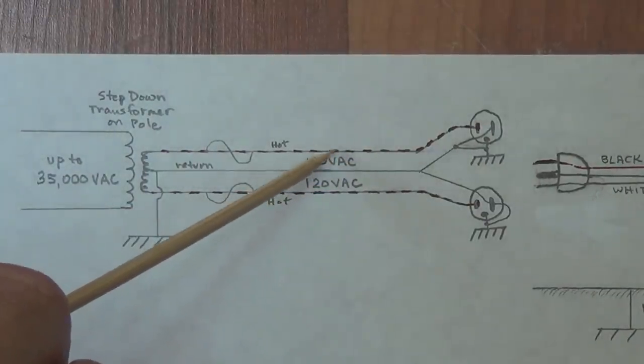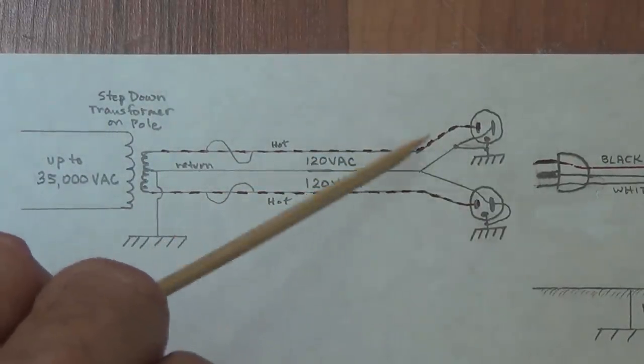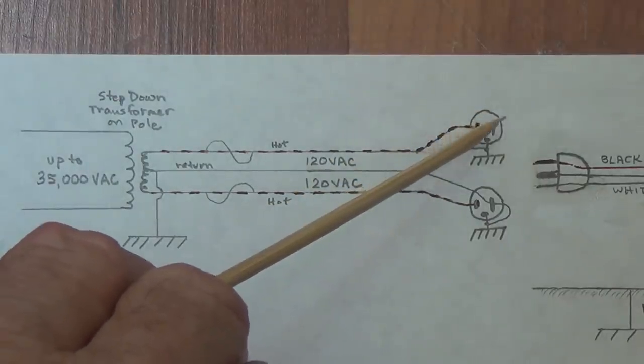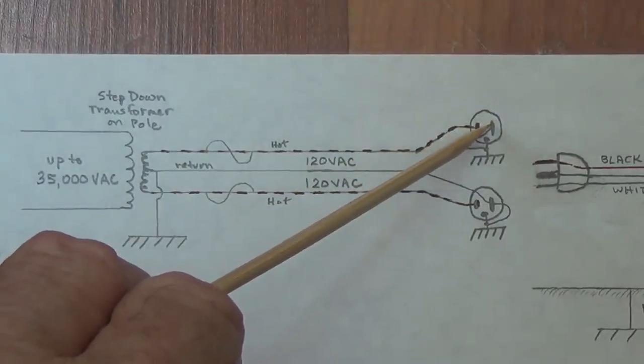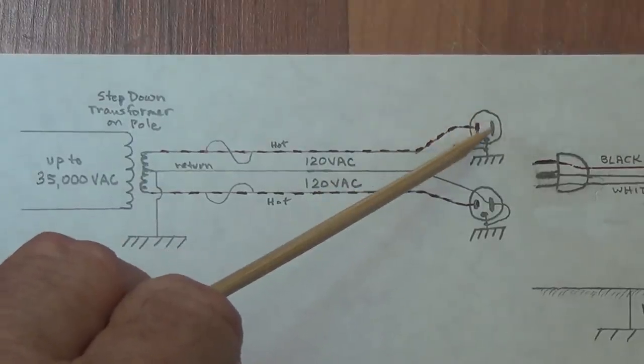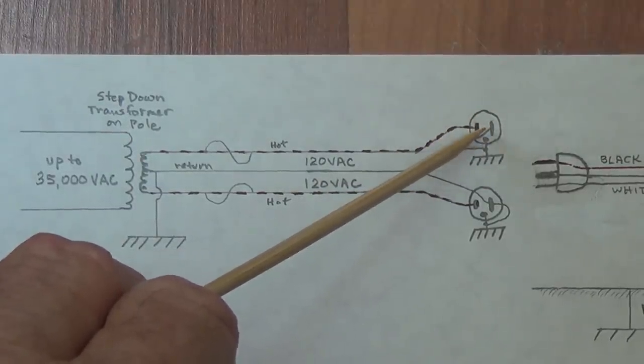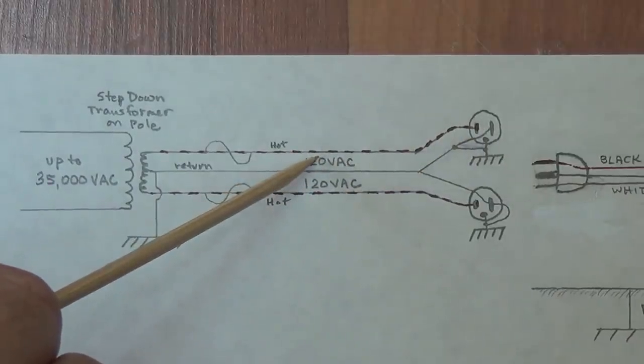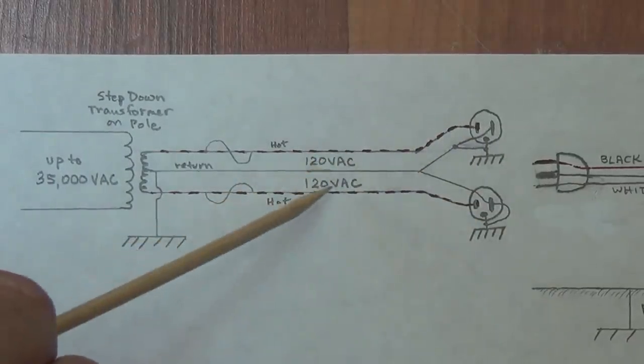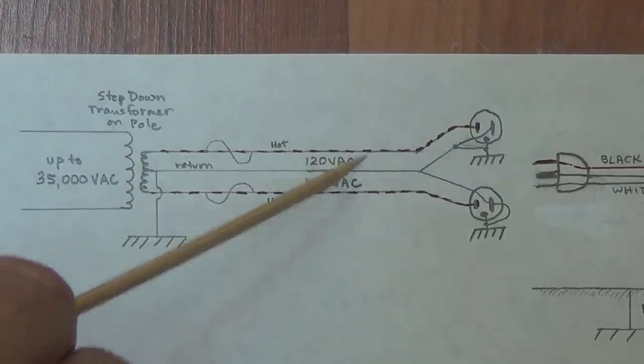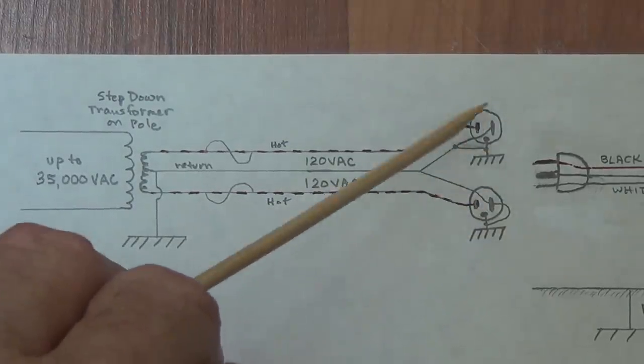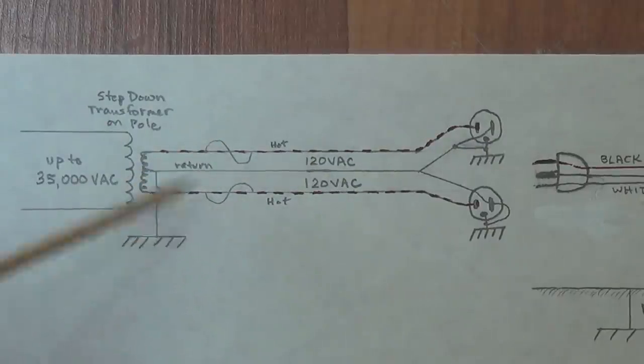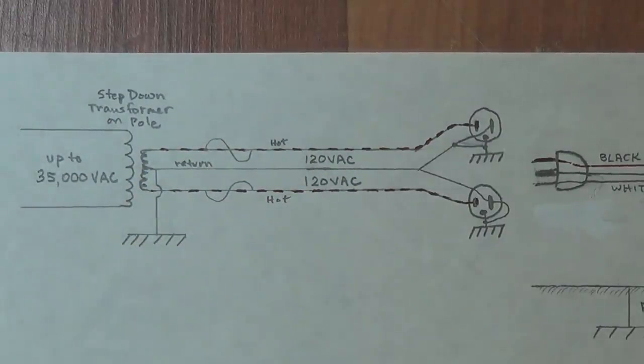Each of the 120 volt AC wires is used to energize half of the wall receptacles in your house. That means that half of your house will have receptacles energized by this wire, the other half will be energized by this wire, and that means that half of your sockets are out of phase with the other half. However, this is not an issue. This is not an amplifier circuit, so for household use, the out of phase condition is not a problem.